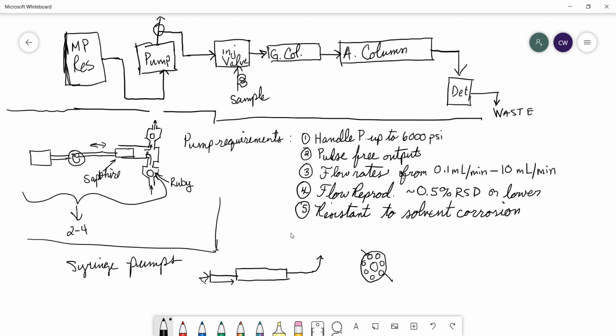From these pump heads, the first thing that happens is we get a pulse dampener. And then depending on your instrument design, you can either have a proportioning valve in front of the pump, or there could be some kind of mechanism to proportion your solvent after your actual physical pump head. It depends on your instrument manufacturer design. Most common, I think, is before the pump. We will talk about sampling valves and solvent proportioning valves in the next video, and I'm going to draw a nice schematic for you as well.